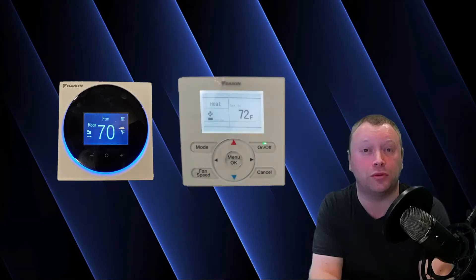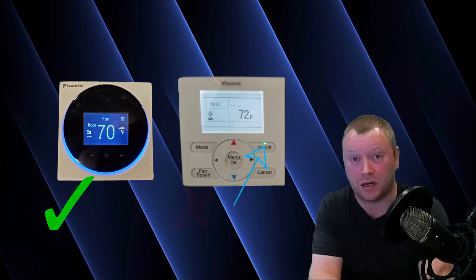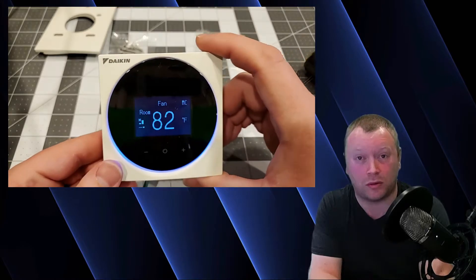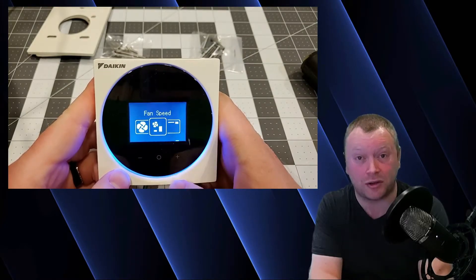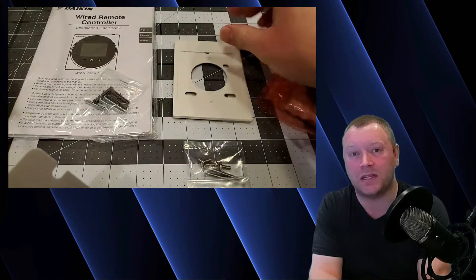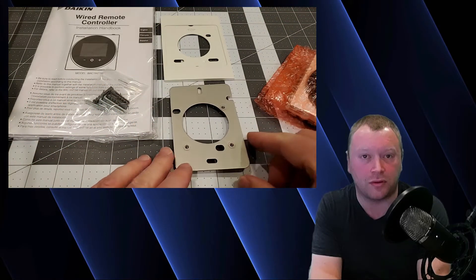So what makes the Madoka so much different from the Nav, other than its looks? Well, for starters, it has a blue LED ring that can be programmed on or off — something the green LED on the Nav Controller could never be programmed for. The Madoka also only comes with one button, which is inconspicuously hidden on the top side corner of the controller. This button turns the controller on or off but serves no other purpose. All user control is done on the touchscreen on the front of the controller. The Madoka can also be mounted flat to the wall, surface mounted, but it comes with a mounting plate in case you need to install it on an electrical box — a valuable accessory the Nav Controller does not come with.